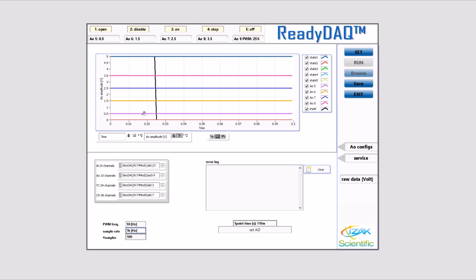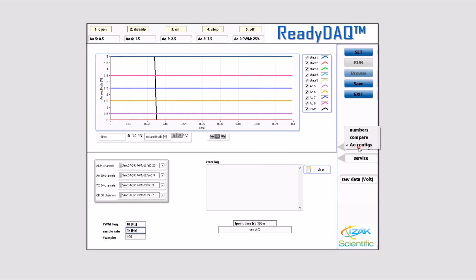Calibration Information. If you use sensors with linear response that connect to your analog input channels, you can write the calibration coefficient in the INI file and exhibit the graphs and the measurements with the physical values set according to the coefficient factor for each channel, slope and offset.